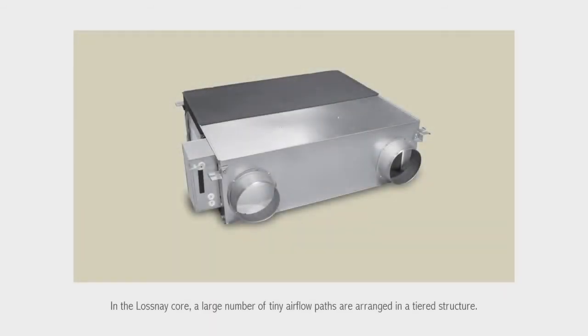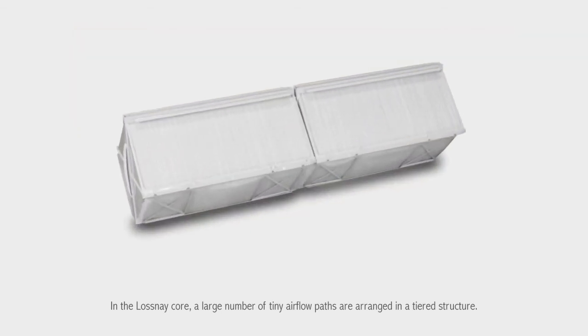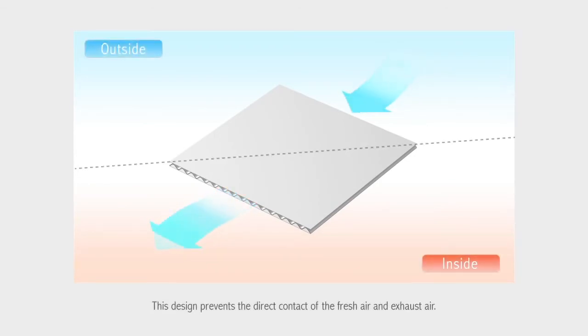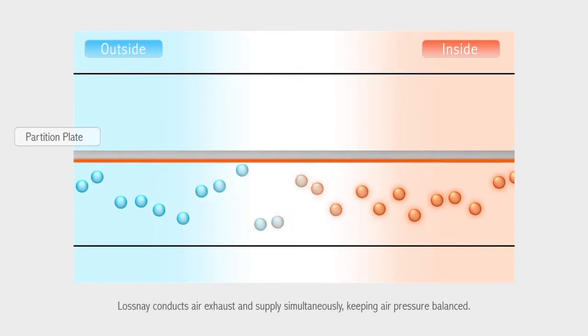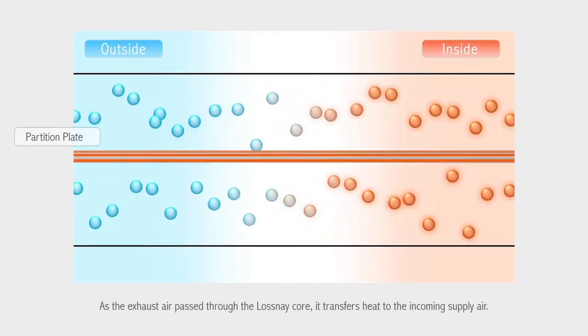In the Lossnay core, a large number of tiny air flow paths are arranged in a tiered structure. This design prevents the direct contact of the fresh air and exhaust air. Lossnay conducts air exhaust and supply simultaneously, keeping air pressure balanced. As the exhaust air passes through the Lossnay core, it transfers heat to the incoming supply air.